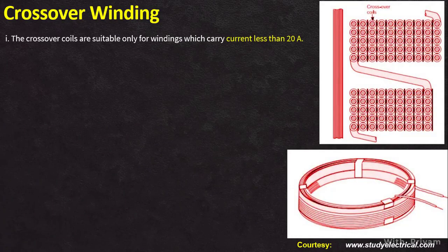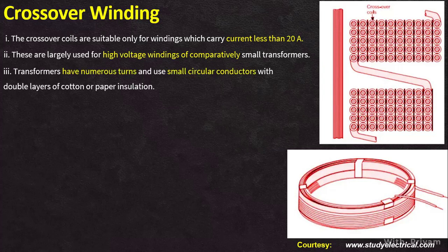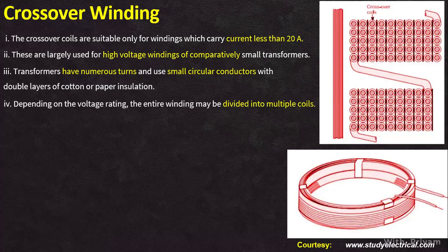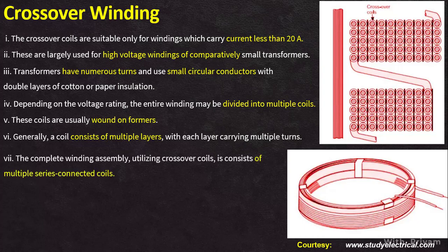Crossover coils are suitable for windings which carry current less than 20 amperes. These are largely used for high-voltage windings of comparatively small transformers. These transformers feature numerous turns employing conductors with small circular cross-sections, covered with double layers of cotton or paper insulation. Depending on the voltage rating, the entire winding may be divided into multiple coils, usually wound on formers. Generally, a coil consists of multiple layers with each layer carrying multiple turns. The conductor can be round or a rectangular strip, and the complete assembly of crossover coils consists of multiple coils connected in series.